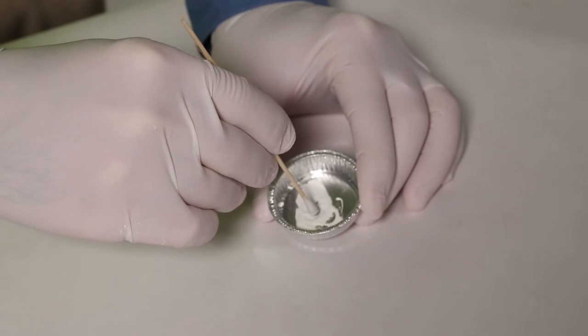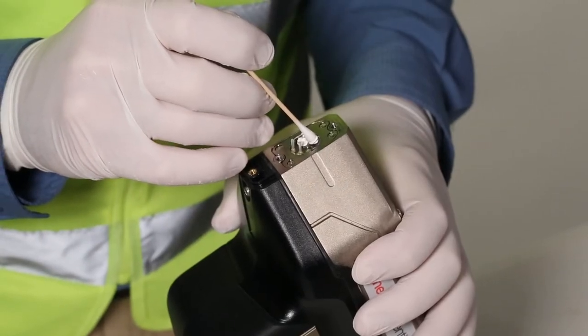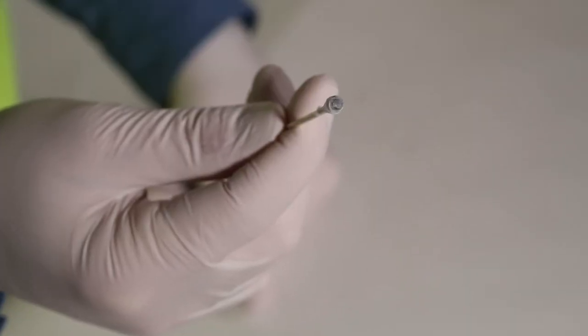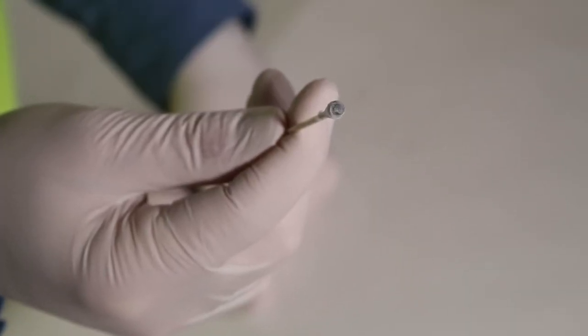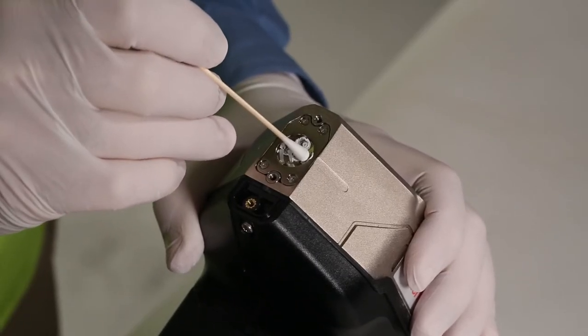Once mixing is complete, dip the cotton swab into the opaline cleaning mixture and apply a small amount onto each of the laser windows. Pay close attention to dirt collection on the cotton swab and replace the swabs as they become dirty. Also, be sure to avoid any of the argon ports.